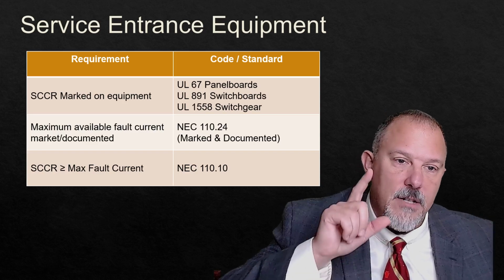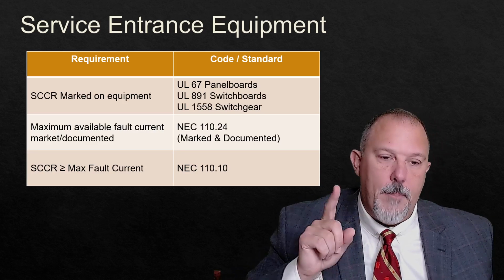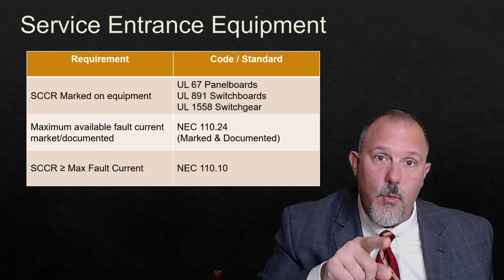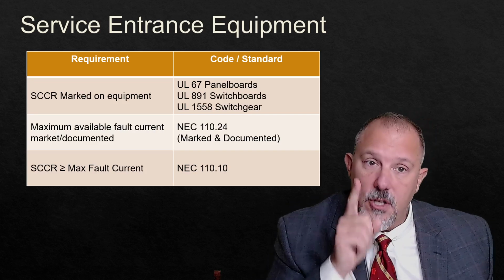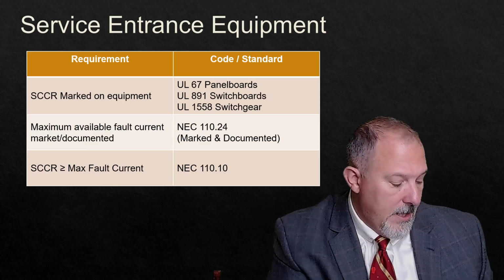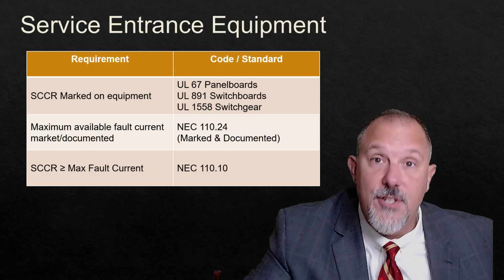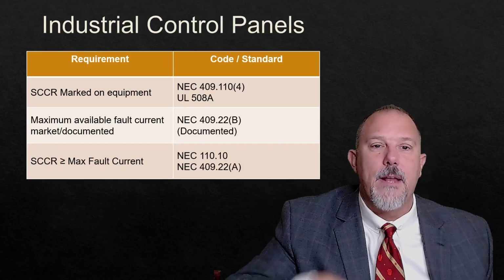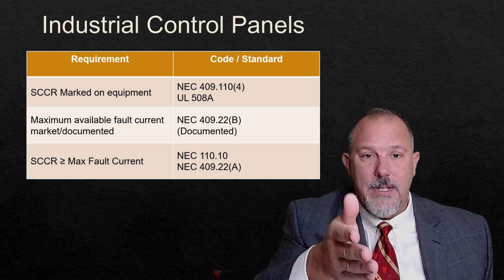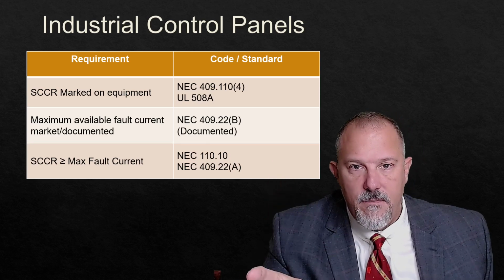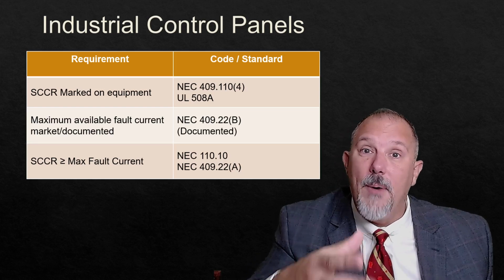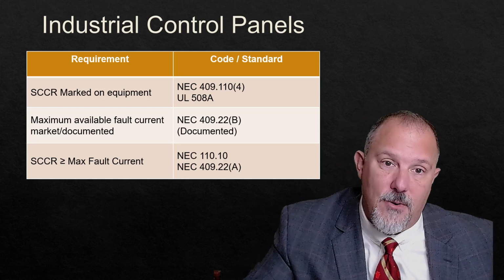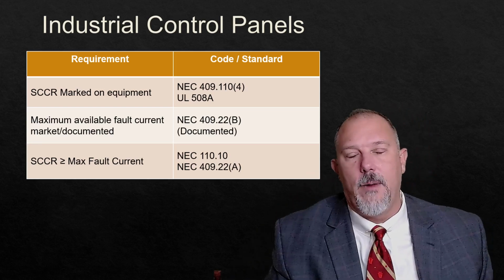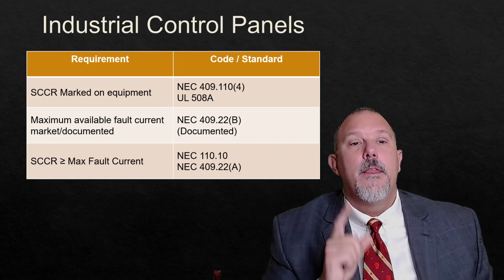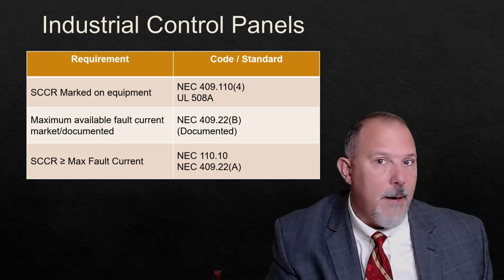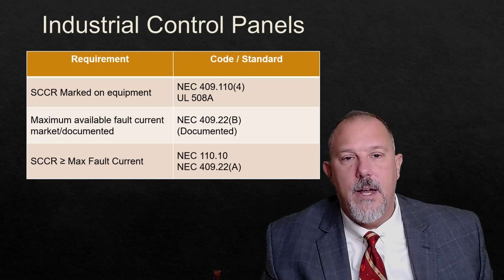So I need to mark the available fault current based upon 110.24 if it's service entrance equipment, but if it's not service entrance equipment, I still have to mark it based on 408.6. Check it out. It's new for the 2020 code. Industrial control panels. Article 409 tells us 409.110.4 tells us we need to mark the SCCR, but if you buy a listed UL 508A panel, it will have the short circuit current rating because it's required by the listing. The maximum available fault current has to be documented, not marked on the equipment, but documented as per 409.22B.